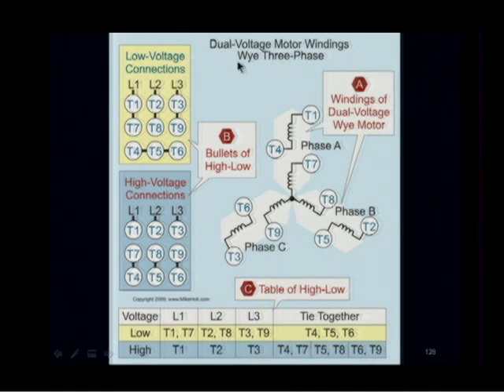So if we have a dual voltage motor and we're going to connect it to line 1, line 2, and line 3, which ultimately goes to T1, T2, and T3, but you have, let's see, 1, 2, 3, 4, 5, 6, 7, 8, 9 terminals. And the nameplate would indicate for low voltage, line 1, connect T1 and T7. Line 2 is T2 and 8. Line 3 would be 3 and 9. And then it says tie 4, 5, and 6 together. So here's an example: 1 and 7, 2 and 8, 3 and 9, and tie 4, 5, 6 together. That'd be your lower of the two voltages.